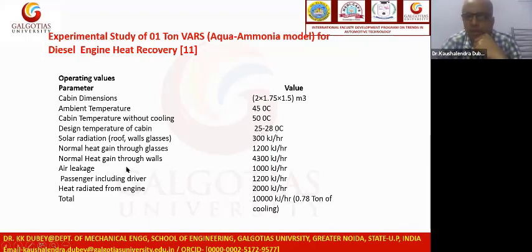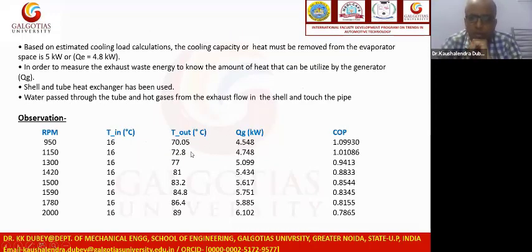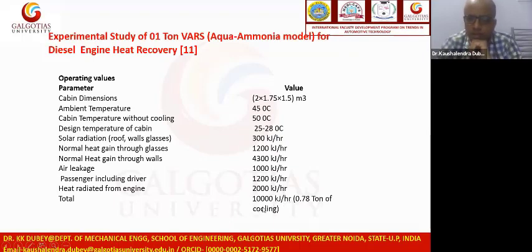So all these things we are adapting to our setup and devices, and some values we have gone through in the ASHRAE table also. So overall, the thermal load is 10,000 kilojoules per hour of cooling. If we convert this to tons of capacity, we need 0.7 ton or 1 ton of cooling for this system. So this is the dimension we have taken for the simple analysis to calculate the cooling capacity of the VAR system for the diesel engine exhaust.